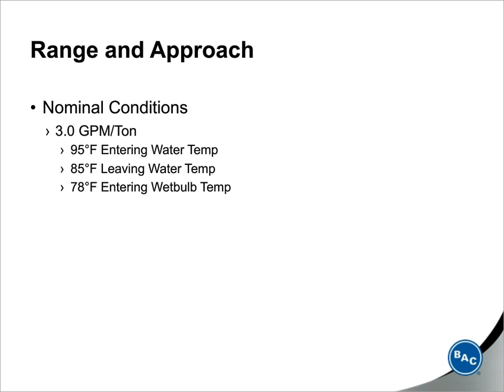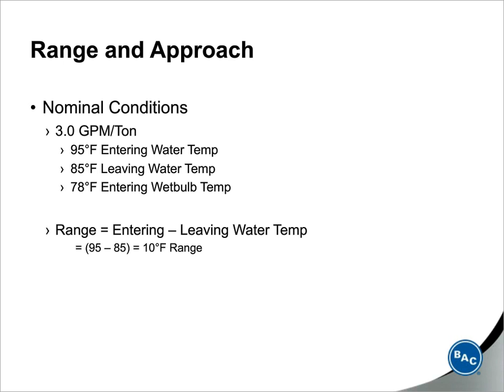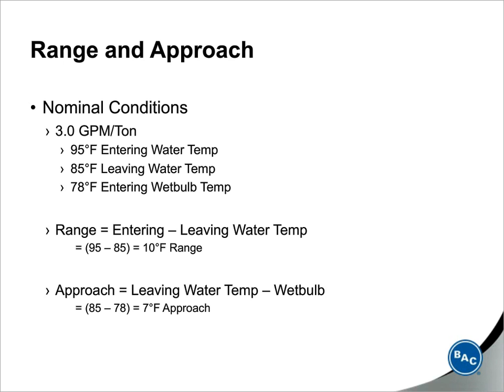Typical for the Northeast. In certain regions in the country, let's say Miami, it may be more like 79 or 80-degree wet bulb, but these are pretty typical design conditions. Now, the range is the temperature difference between the water entering and leaving the cooling tower. So in this particular case, it's a 10-degree range. The approach is the difference between the leaving water temperature and the outdoor ambient air wet bulb temperature.